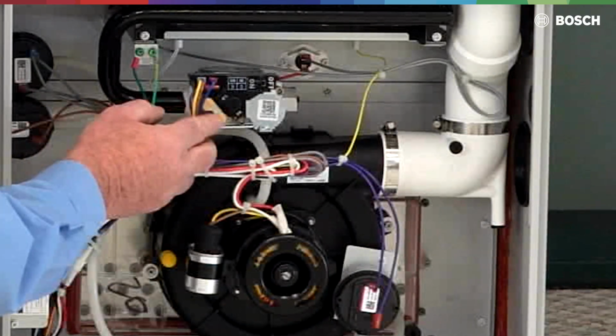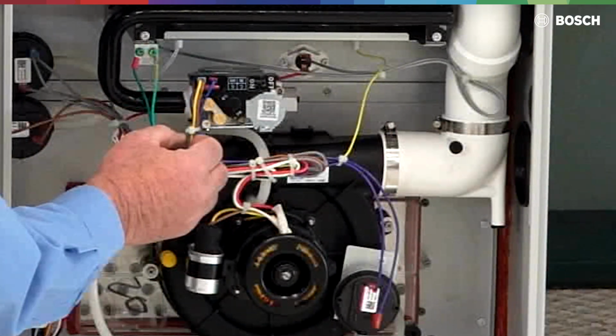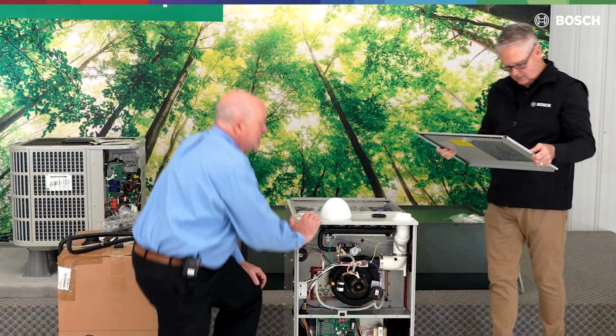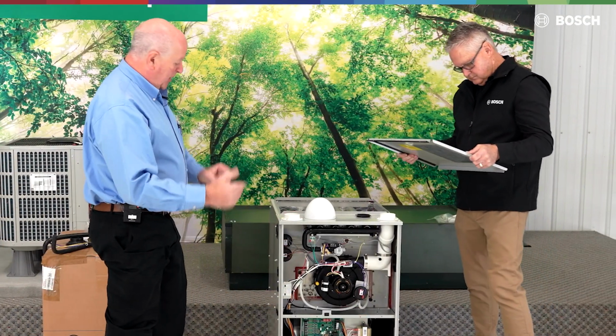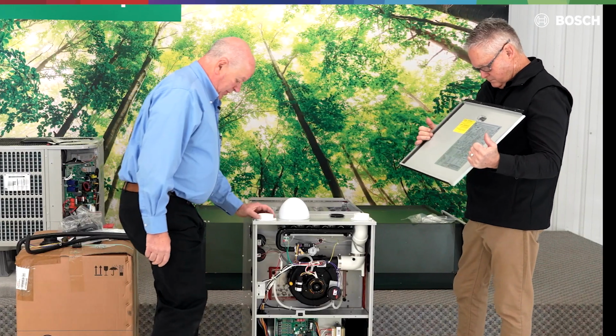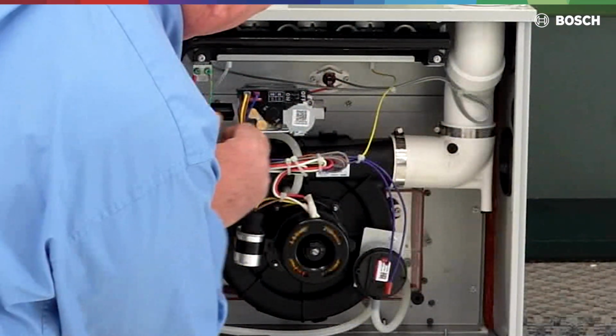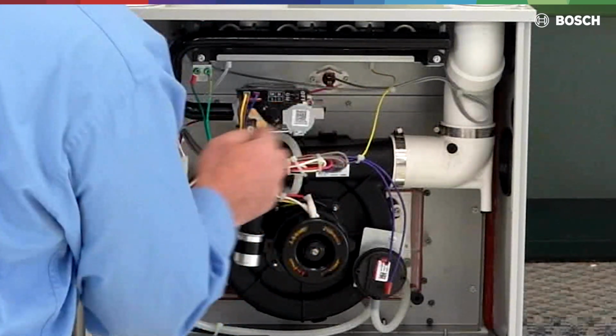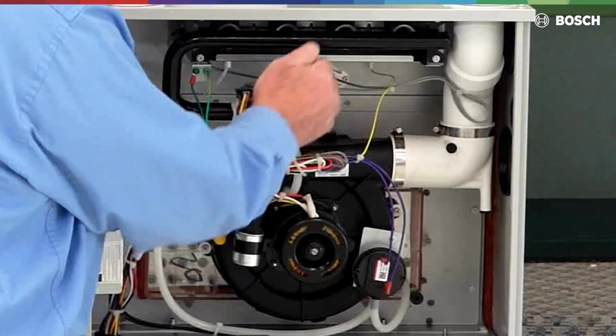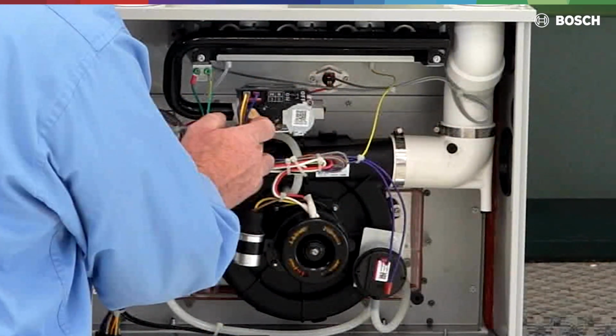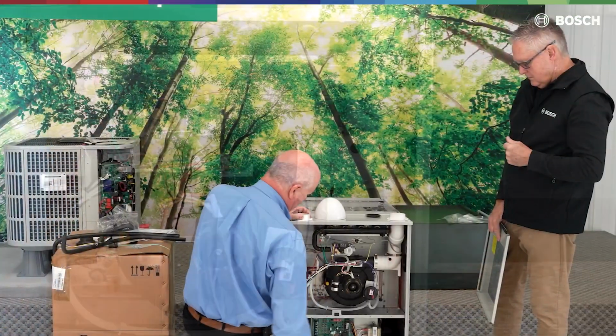There's a count of turns. We take out the old springs, then screw in the new ones, and the kit tells you how many turns to adjust to get your pressures. We have a manometer that hooks up to ports here. We have our incoming gas pressure here and our secondary pressure here. We need to make sure we have enough incoming gas pressure, and we can set the secondary pressure on that process.